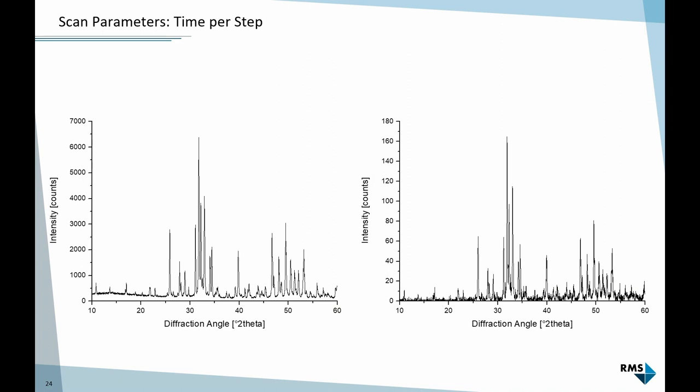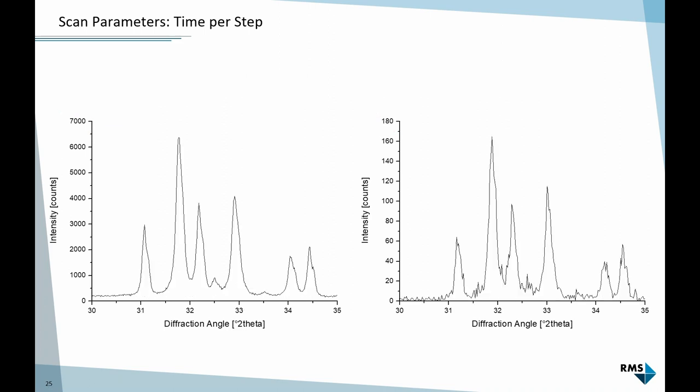The third parameter is time per step. It's difficult to make a general statement because the two diffraction patterns here were measured on different instruments but both in 12.5 minutes. On one we get 7,000 counts, on the other 180 counts. The difference is the left was measured on a linear detector, a rather modern detector, and the right on an old point detector that's less effective and takes much longer to reach the same intensity. I can't really tell you how long to measure per data point without knowing what instrument you use, but I can give you some personal experience.